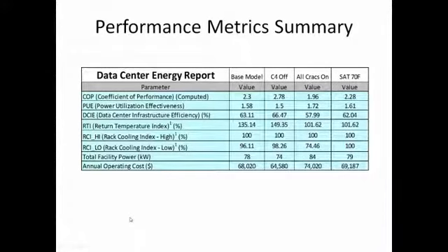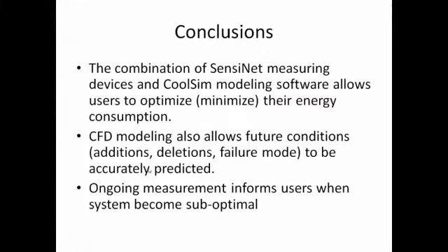So this particular design in the early stages wasn't that far off, but that shouldn't surprise us, Scott, because it had containment in it, and it had been designed to be efficient, I think, as a pod. But again, we were able to iterate to get it to a more optimal design once we validated the CFD run. So I think, again, it shows that using the two in combination is a very, very nice way to go.